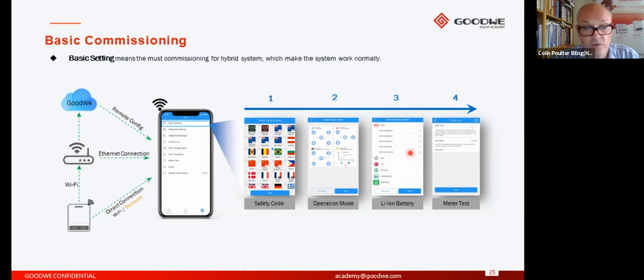Now the appropriate battery here will either need to be selected, or lately there is some self-detection of batteries as well. However, after that battery selection has been made, you then step onto the next screen by pressing next, when you will arrive at this section called meter test. Now, providing that you have installed everything correctly, when you perform this meter test, this is going to indicate to you whether you have connected the CT clamp onto the incomer correctly. If you haven't, it's going to tell you. However, this does require that everything is correct.